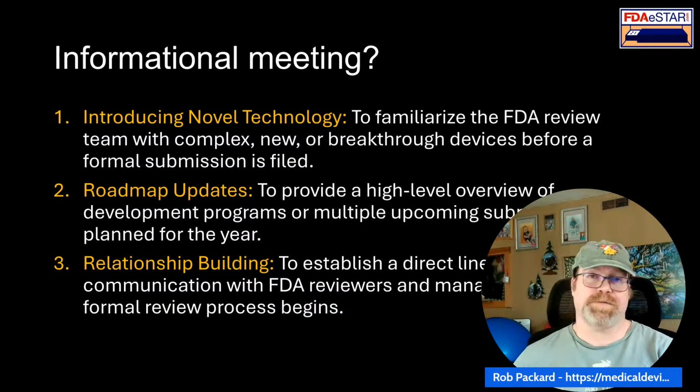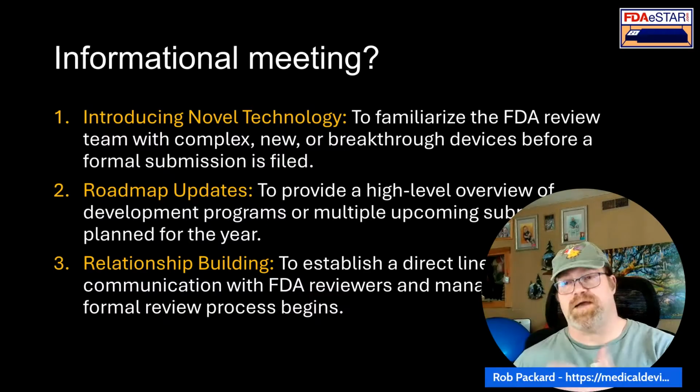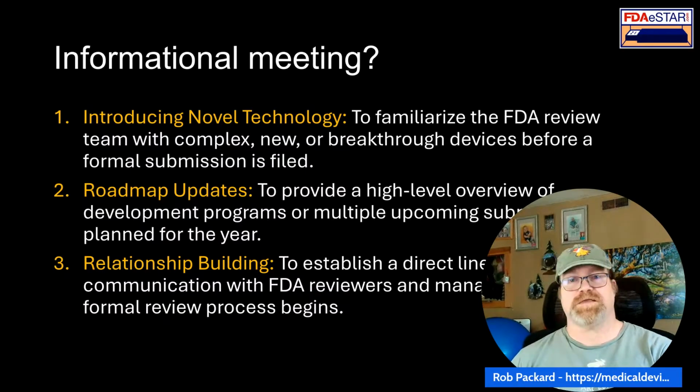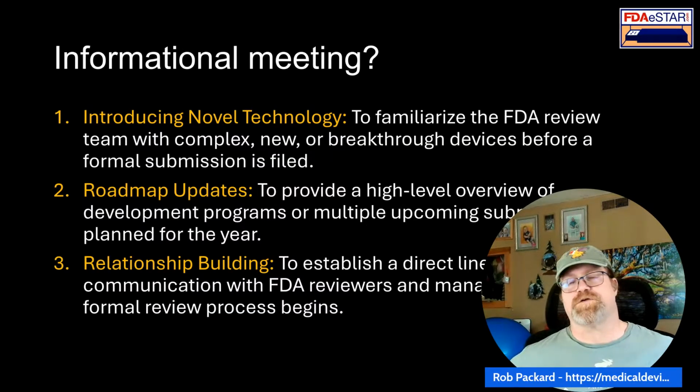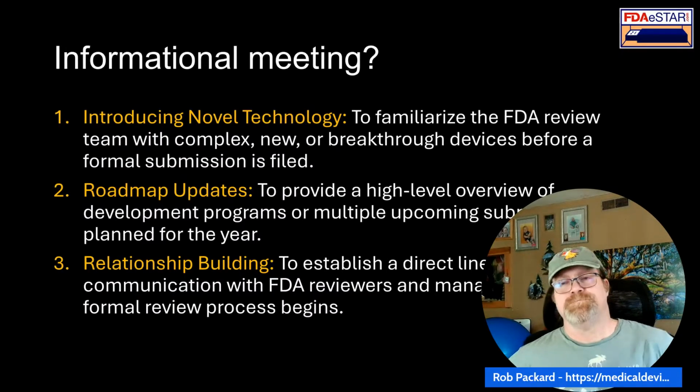But a lot of people aren't familiar with that because they haven't gone down that de novo pathway for an IVD. So they think they can just combine the two, and the FDA says, no, sorry, you've got a problem here for your regulatory pathway. You cannot combine these 510(k) tests with your de novo test in the same de novo submission. You have to get one, and then you can submit the other.